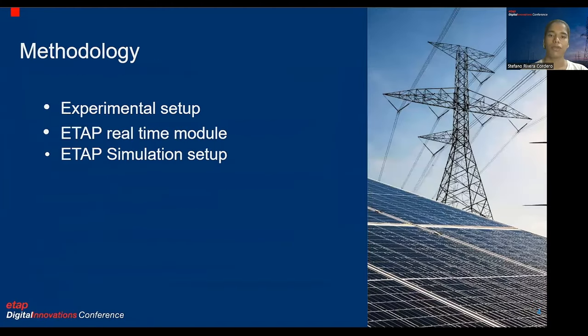The methodology we use consists of an iterative process of three steps: measurement of the real circuit, visualization through ETAP Real-Time, and simulation of the network in ETAP. With each iteration, the aim is to adjust the parameters of each component of the system with high precision until the simulated load is as close as possible to the real one.